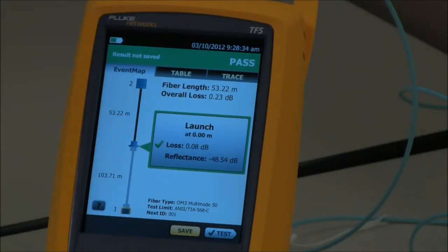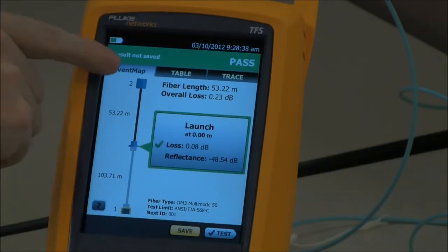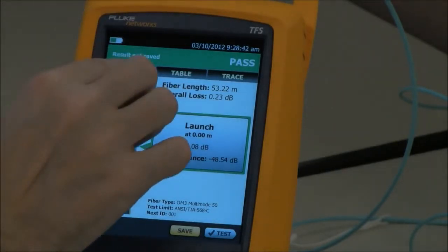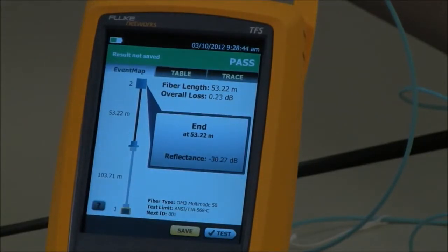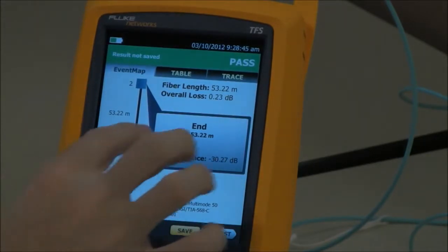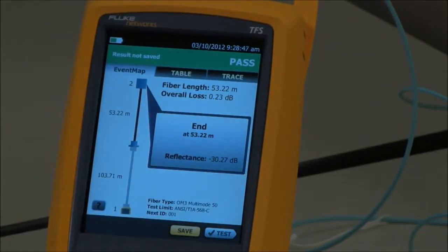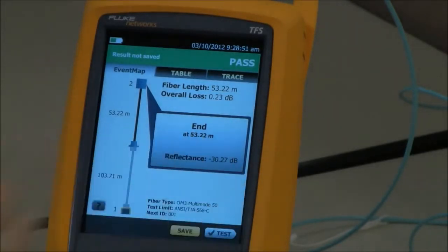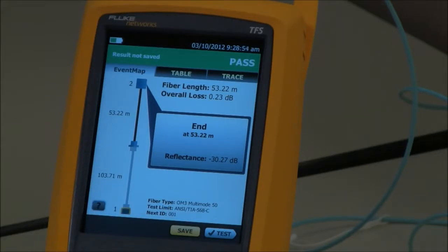But because I didn't use a tail fiber, I don't know how good the connection is at the end of the link. If I tap where the connection is at the end of the link, you'll notice that I don't see a loss value because I didn't use a tail fiber. What you will see is a reflectance value — in this case, minus 30.27 dB.